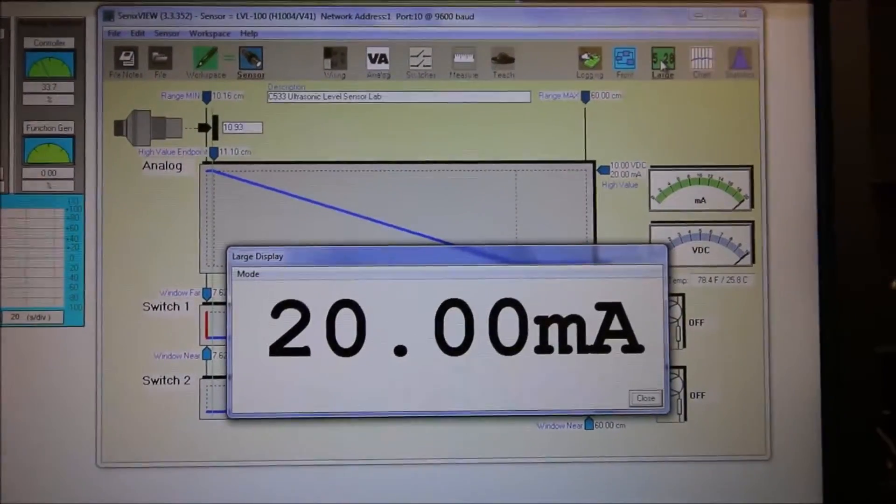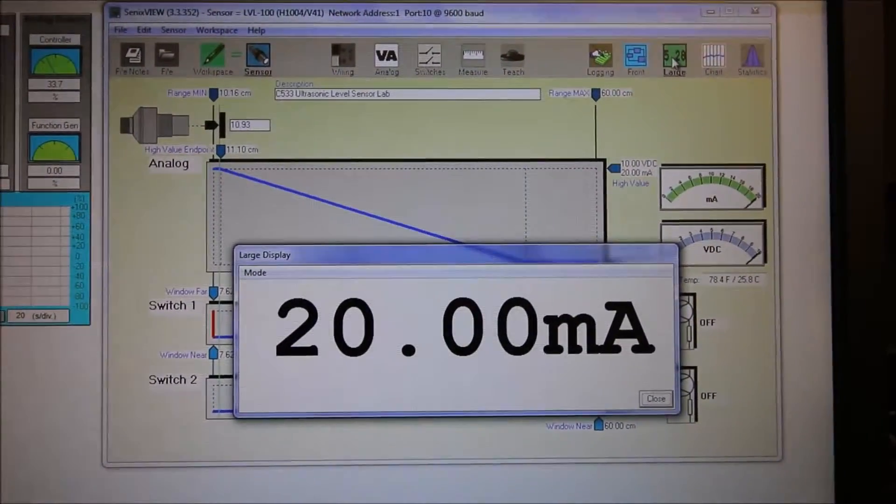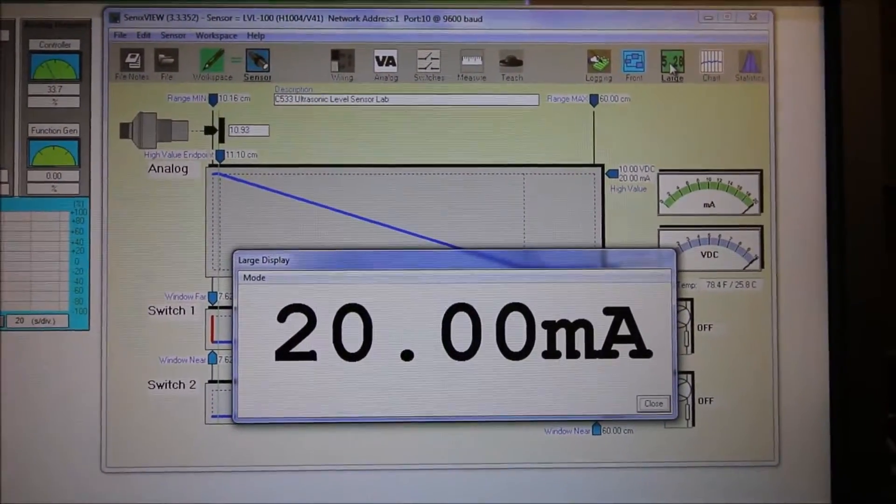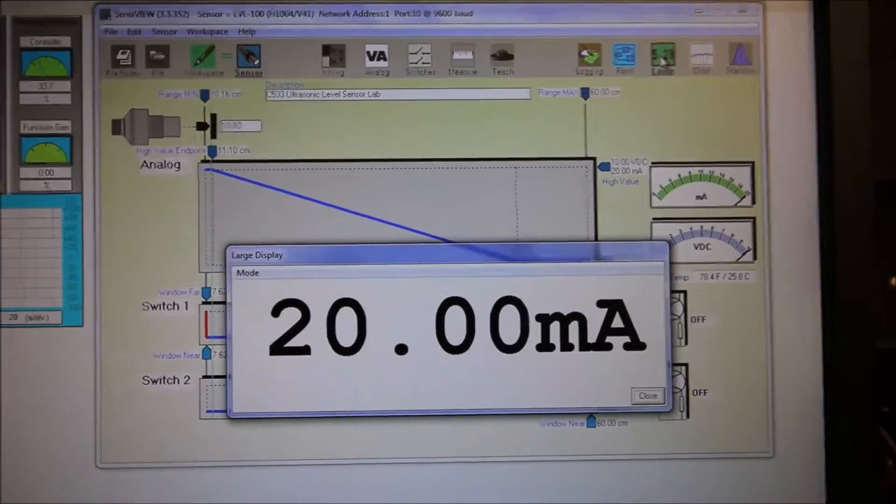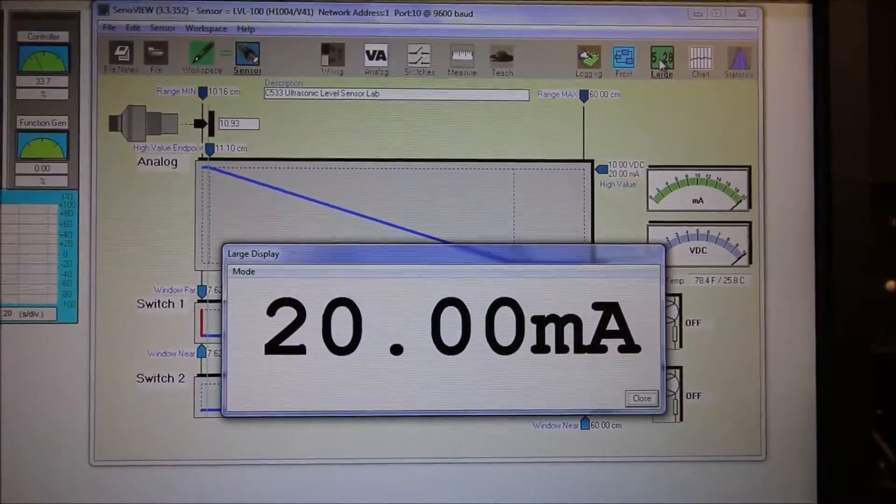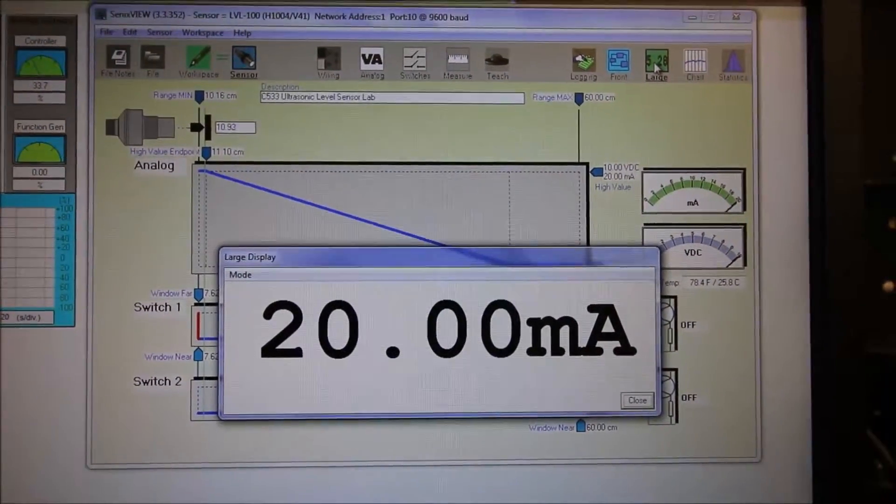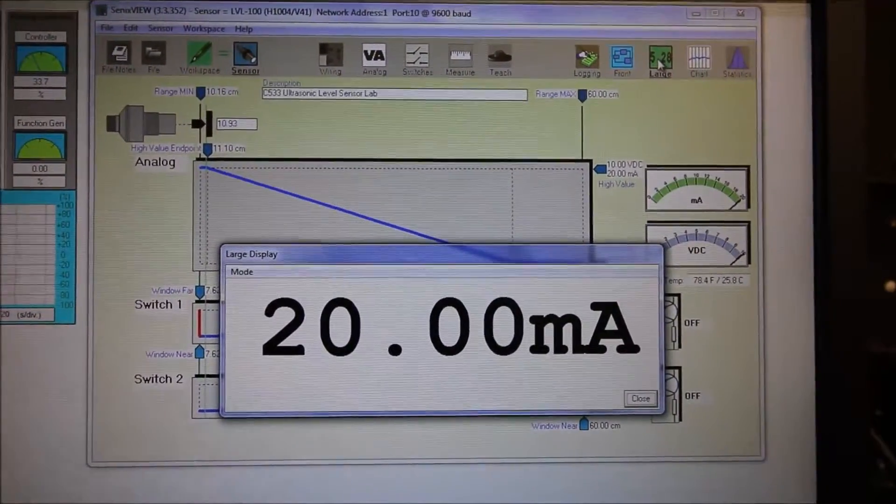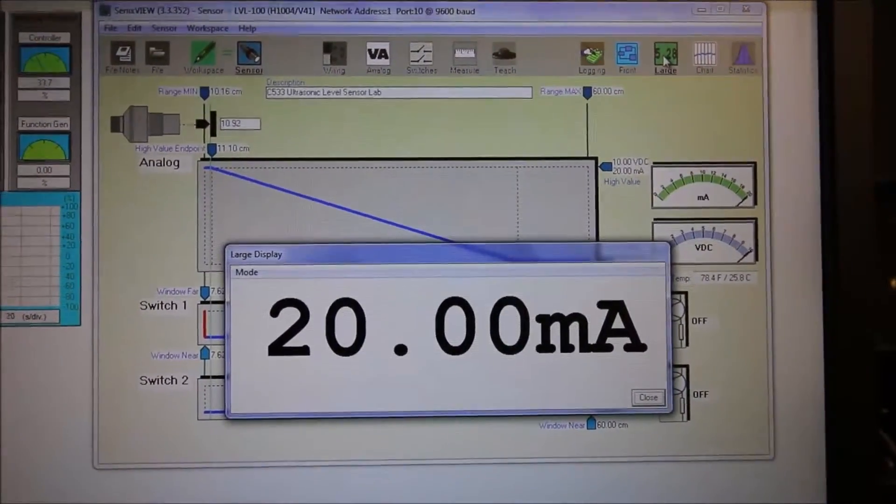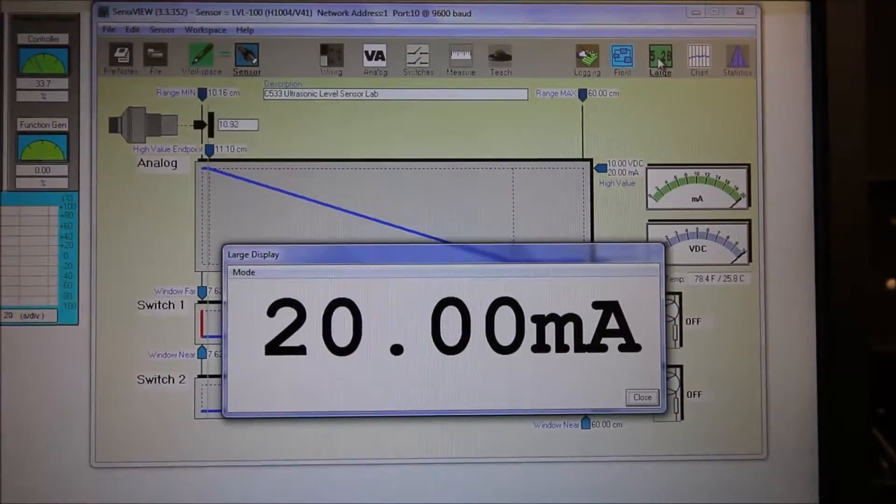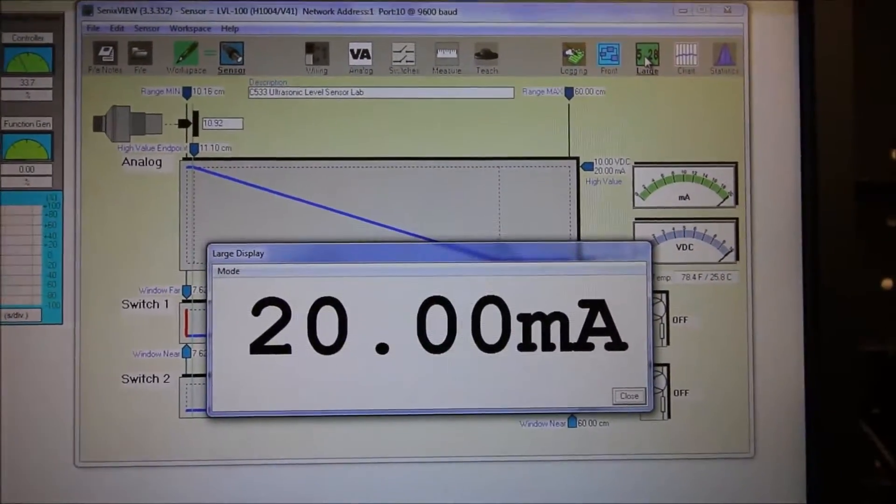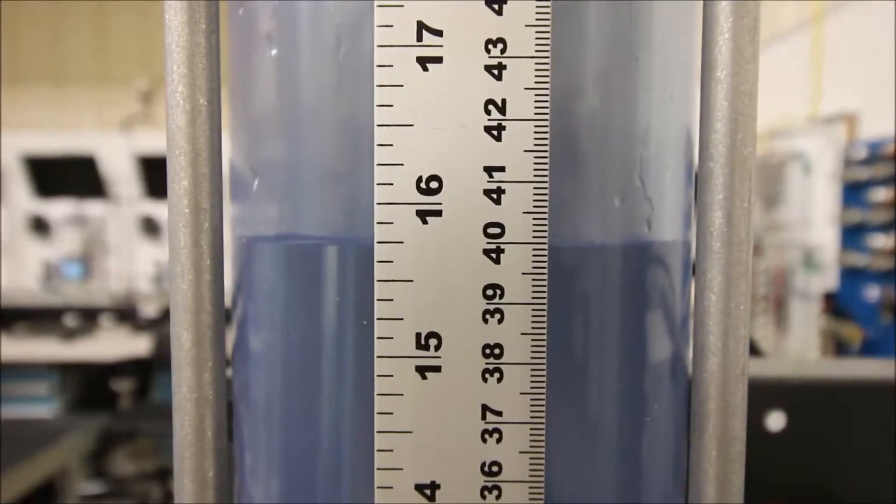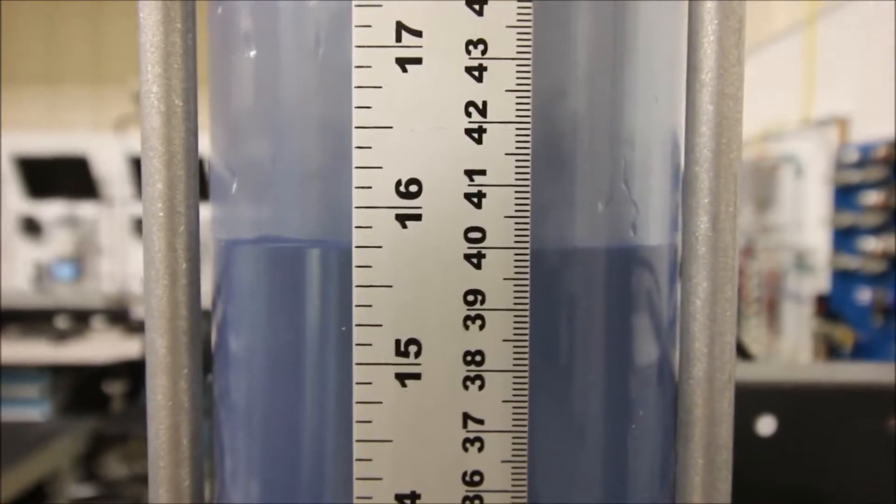Okay, let's drop it down by increments of 10 centimeters and we'll see the values of current that's coming out of the sensor. If I drop this down another 10 centimeters down to 40 centimeters, I should be getting 16 milliamps out.